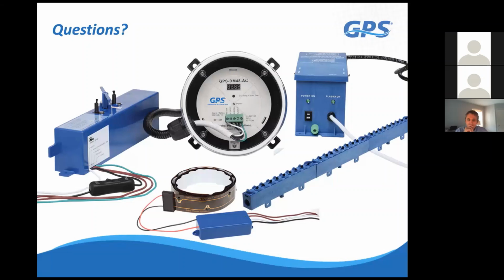So we can make, let me back up. We'll make the really small particles larger, but if you look at this in a controlled environment, in a clean room, let's say you start off at a certain particle level at 0.3 microns, when you turn the systems on, you will actually see the 0.3 micron particle counts generally increasing, like we're generating particles, because we're taking the particles that the meters cannot read and shifting them, making them larger. So now they're showing up as the smallest particle the reader can read, which is 0.3 microns. And we continue that shift, and then over a period of minutes or hours, the 0.3 micron particles start going down because now we're shifting them larger. Some could settle out of the air with poor air exchange rates, and some are going to get back to the filter and be removed.